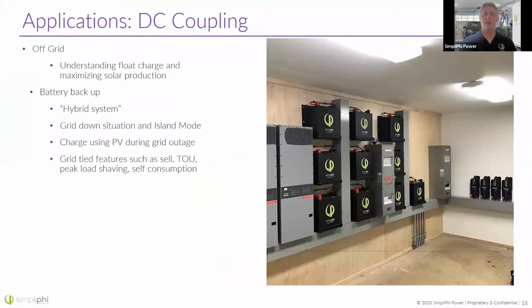So if you're off grid, I think DC coupling is usually the way to go. One thing to keep in mind, however, is you need to maximize your float charge. So if you're off grid, you want to go to bed with a full battery bank. You don't have the ability to use the grid anytime your battery bank is depleted. So you want to make sure that before the sun goes down, you've been in float charge mode all day until then, maximizing your solar production so that you don't begin drawing on your battery bank before the sun goes down.